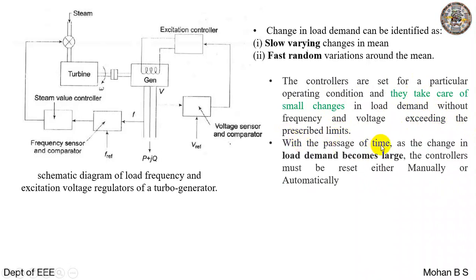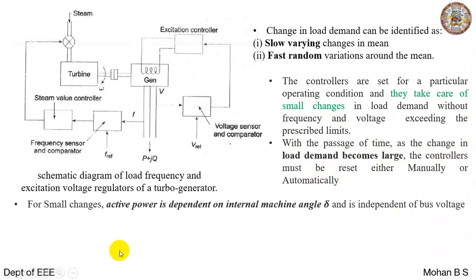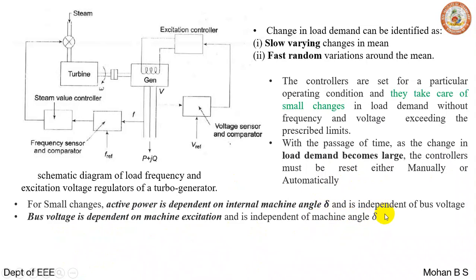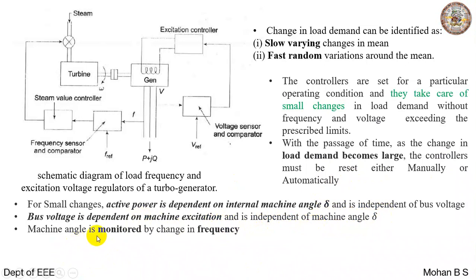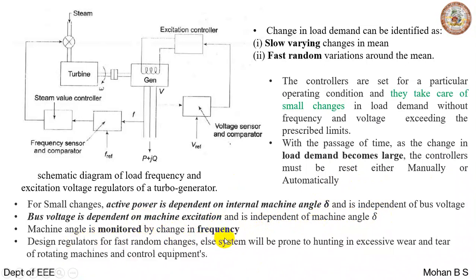With the passage of time, as the change in load demand becomes larger, the controllers must be reset either manually or automatically. For small changes, active power is dependent on internal machine angle and is independent of bus voltage. Bus voltage is dependent on machine excitation and is independent of machine angle delta. Machine angle is monitored by change in frequency. Regulators must be designed for fast random changes, else the system will be prone to hunting and excessive wear and tear of the rotating machines and control equipment.